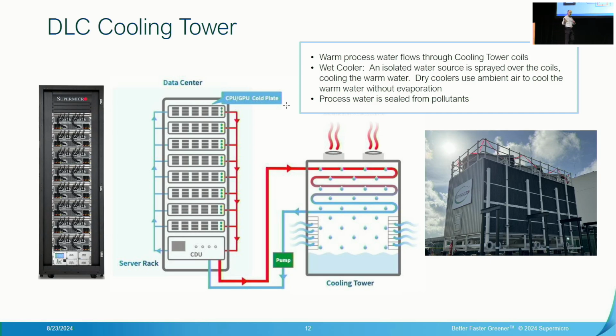So we talked a little bit about what happens at the rack. Cooling tower -- many of you may see, as an example of one of the ones we have at Supermicro, these cooling towers outside of factories or outside of data centers, kicking up all this white stuff. That white stuff is steam, not pollution. It's steam, because this warm water from inside the facility that's been warmed up by the racks is getting pumped outside, and depending on the ambient temperature, if it's very cold outside it'll cool naturally.